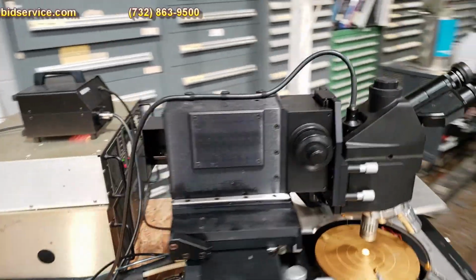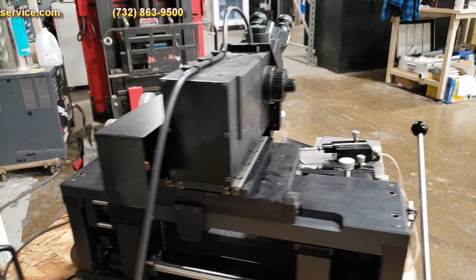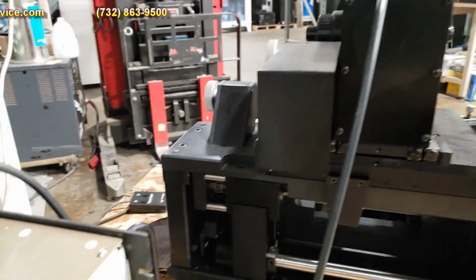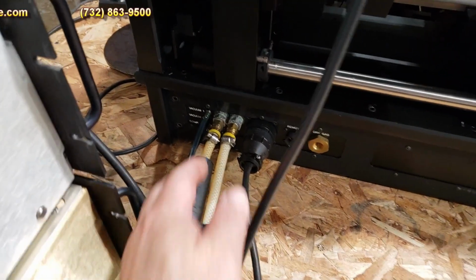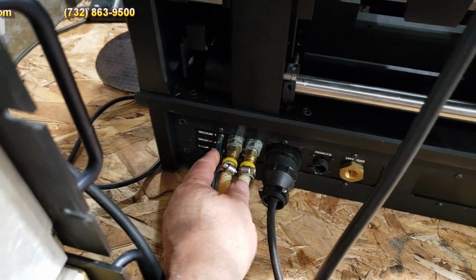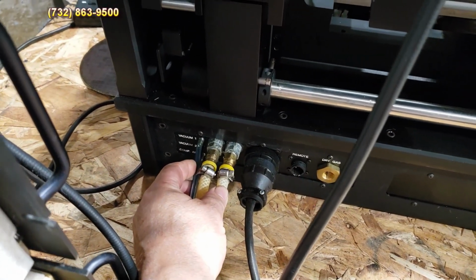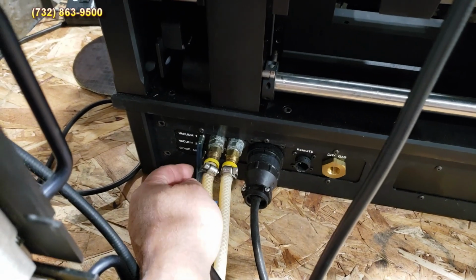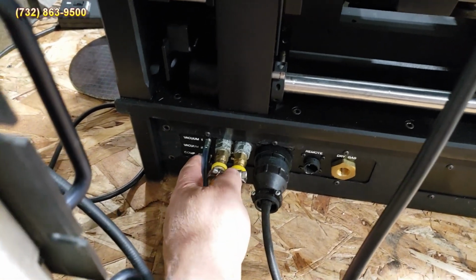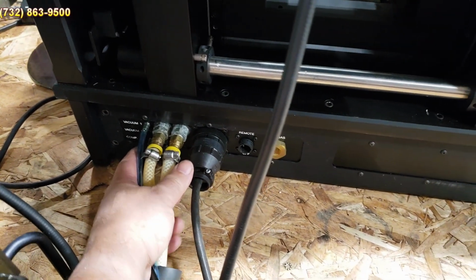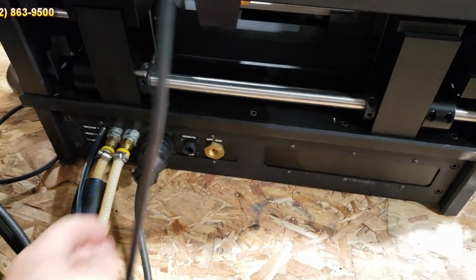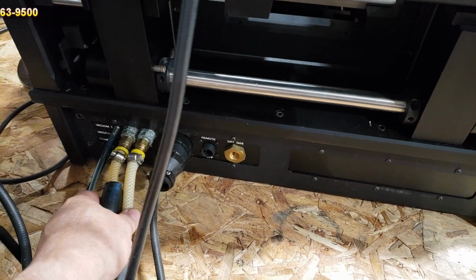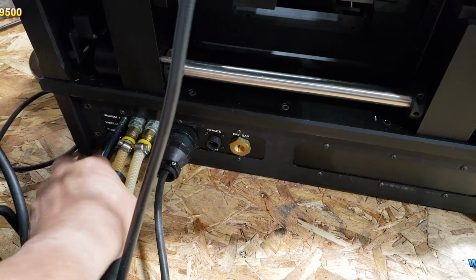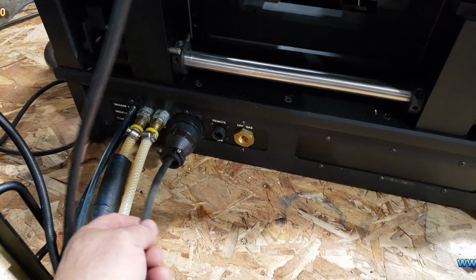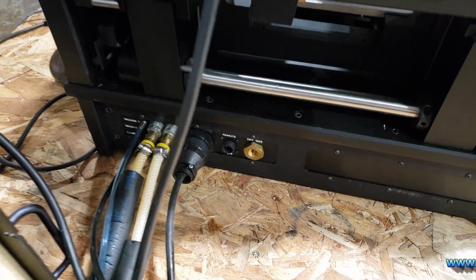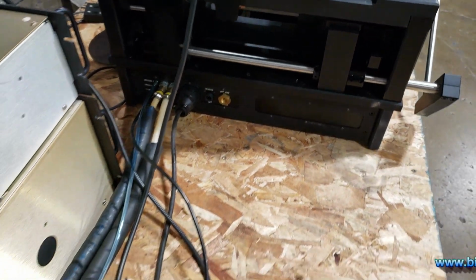Let's go to the back of the system. Okay, on the back of the system here we have your 2 vacuum hookups. One's for the probes and one's for the chuck. Top is for the chuck, 2 is for the probes, and then you have compressed air down here. Here you have your water lines that go into your chuck to cool it down, and then you have your regular connector here that reads the temperature and it also has the heaters.